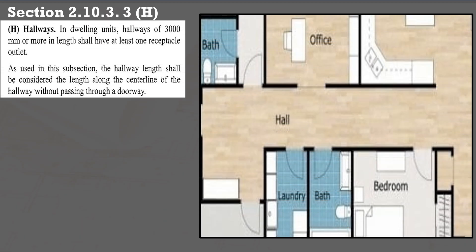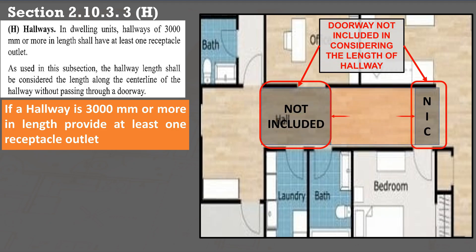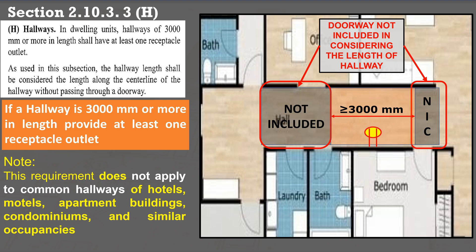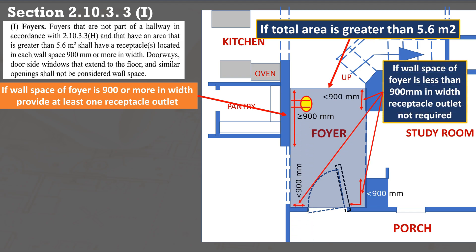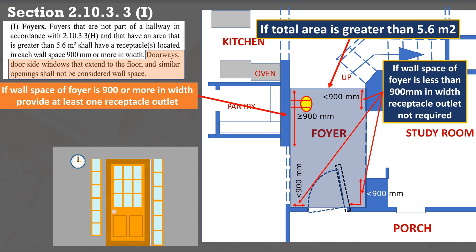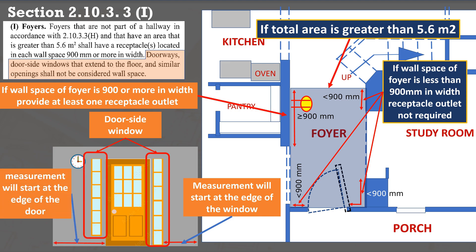For dwelling unit hallways as stated in subsection 2.10.3.3 H, if a hallway is 3,000 mm or more in length, provide at least one receptacle outlet. The hallway length is measured along the centerline without passing through a doorway. This requirement does not apply to common hallways of hotels, motels, apartment buildings, condominiums, and similar occupancies. If foyers are not part of the hallway and have an area greater than 5.6 square meters (60 square feet), a receptacle outlet is required in each wall space 900 mm or more in width. For doorways with door-side windows extending to the floor, measurement starts from the edge of those windows; if they do not extend to the floor, measurement starts from the edge of the door.